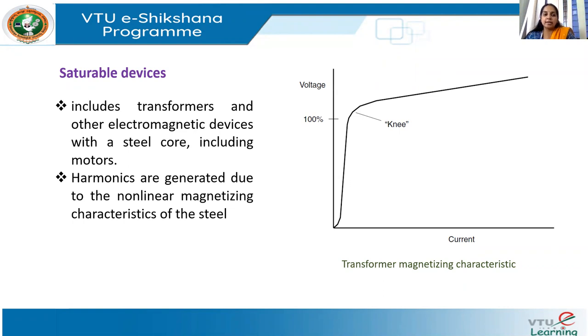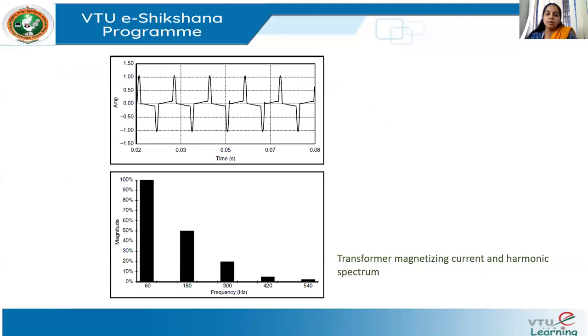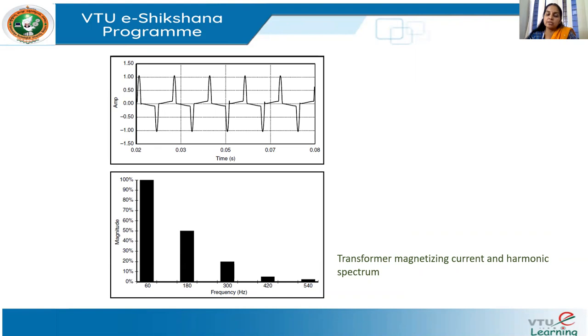Saturable devices mainly include transformers and other core electromagnetic devices, including motors. At times, motors can get saturated and become non-linear loads. The harmonics are generated because of the non-linear magnetizing characteristics of the core. A waveform showing the transformer magnetizing current and its harmonic spectrum reveals that although the supply and output are sinusoidal, the magnetizing current when measured has an almost pulse-like shape.